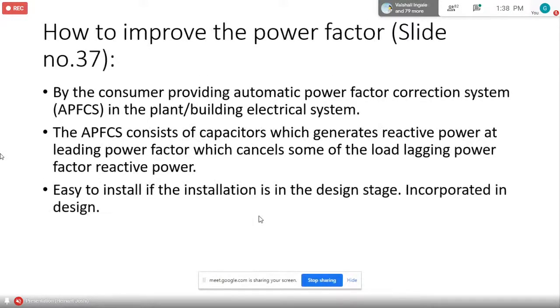How to improve the power factor? By the consumer providing an automatic power factor correction system, APFCS, in the plant building electrical system. So very, very simple. This system consists of capacitors which generate reactive power at leading power factor, which cancels some of the load lagging power factor reactive power. Easy to install if the installation is in the design stage. You can incorporate it in the design and do it.